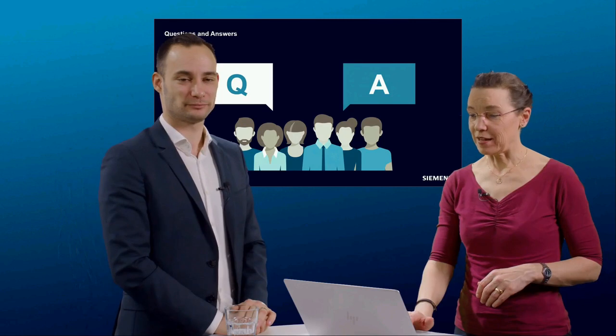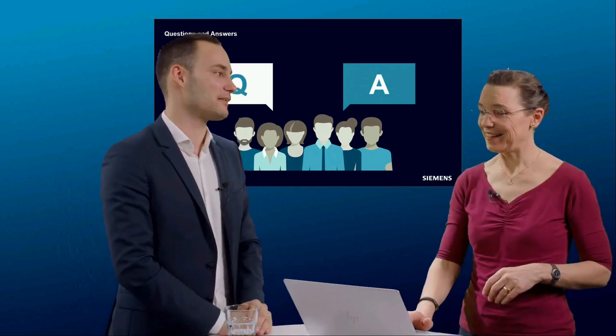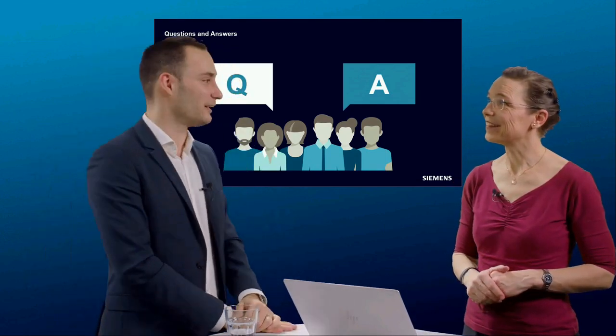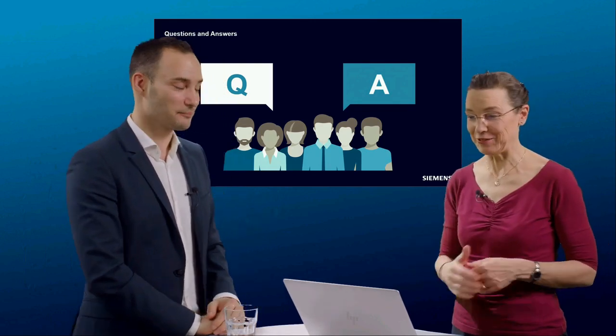Thank you. And ER wants to know, how is the contact erosion measured? So we are using some very fancy formula. I will not display too much today. Basically, when we are opening the breaker, we get the info on which type of current was there when we opened, and when the current disappeared. So it gives us the current over time, and then we just estimate how long it takes, and then we give the right answer. Sophisticated calculations behind, right? Not that much. It's widely known from all the medium-voltage switchgear. We are just using the fruit of our cooperation with the colleagues, and that's really useful for us. Yes, use the data. As always, data is the new gold.